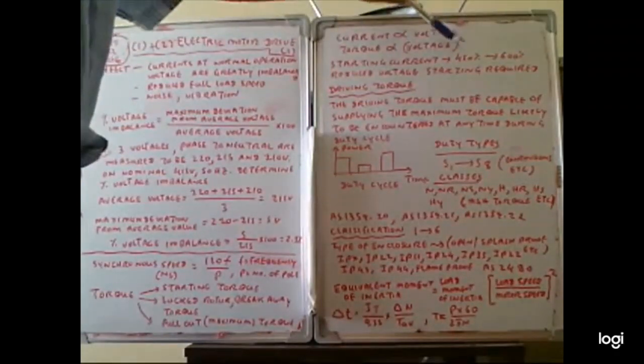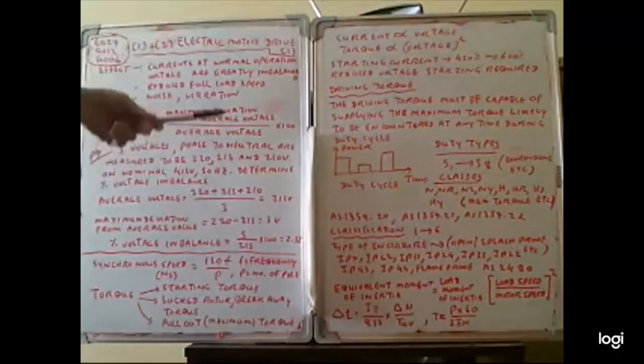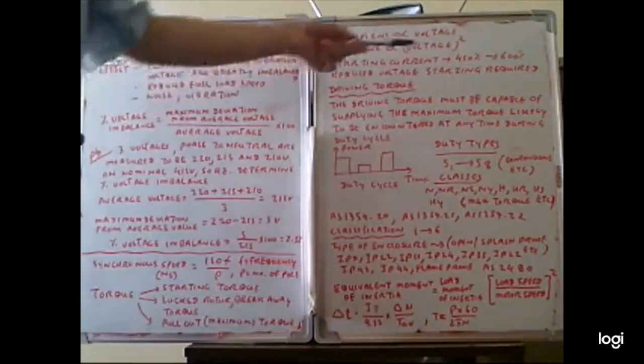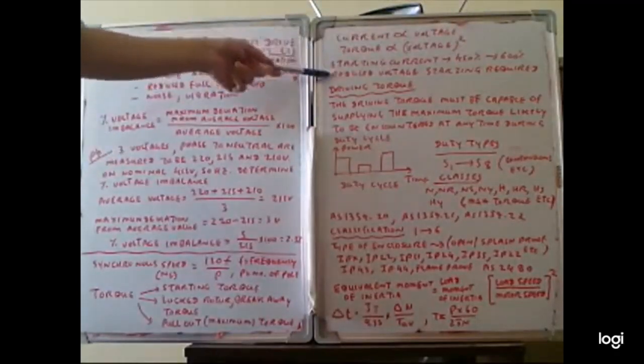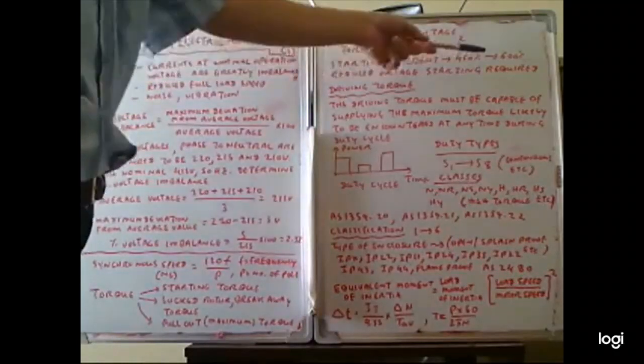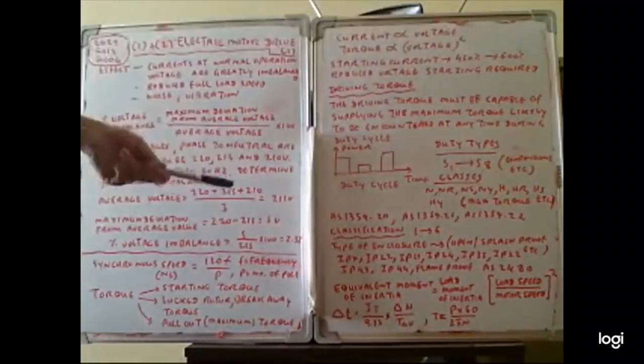The current flow from the supply is proportional to the voltage, and the torque is proportional to the voltage squared. So the motor current is proportional to the voltage, and motor torque is proportional to the voltage squared. The motor starting currents are typically 450% to 600%. Therefore the starting current is higher, so we have to utilize a reduced voltage starting method to reduce the starting current.